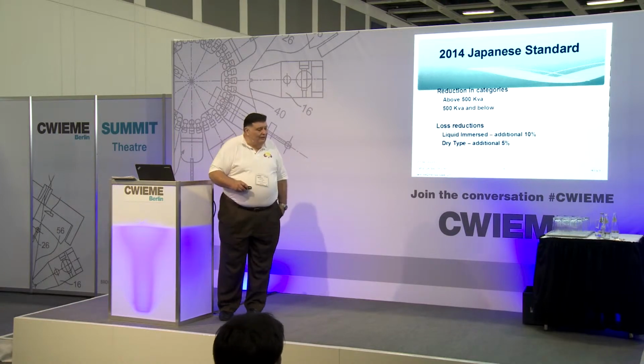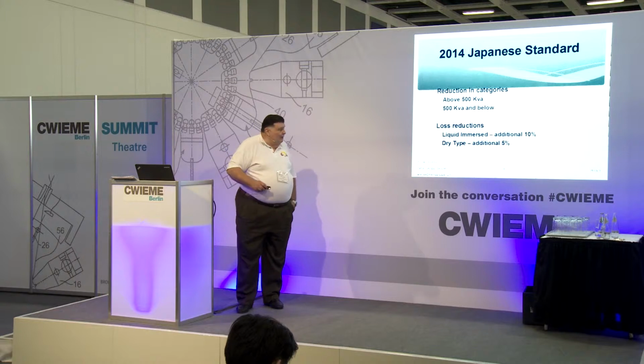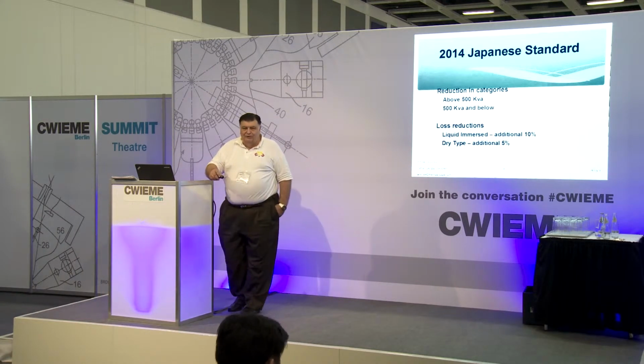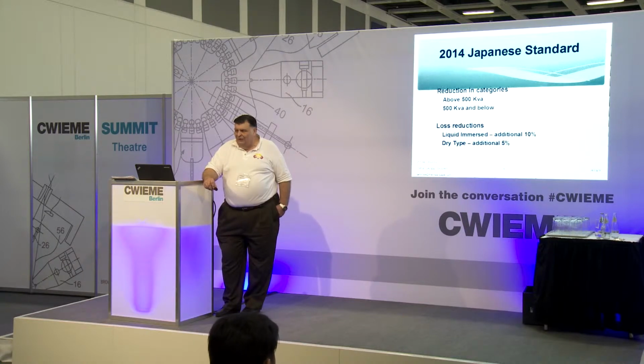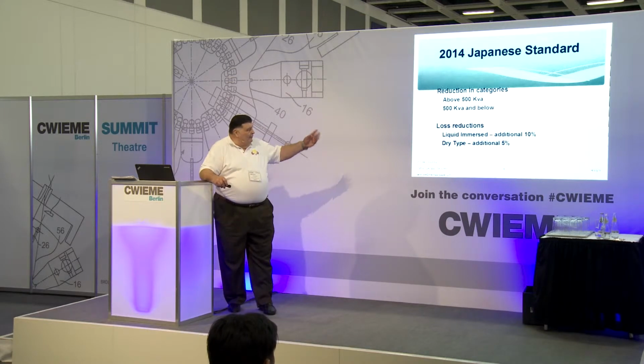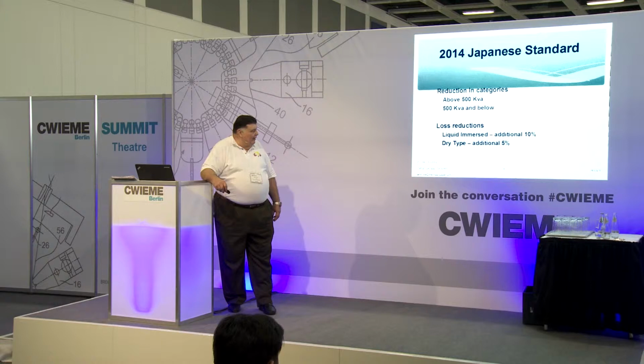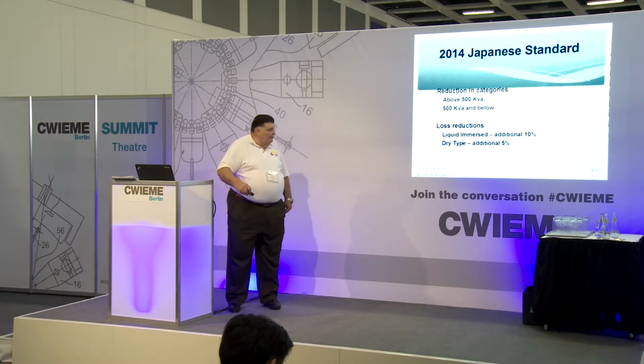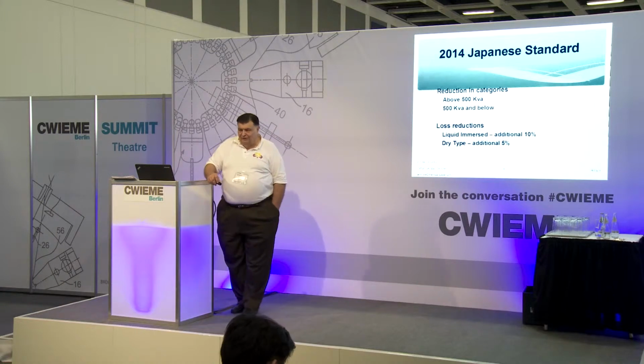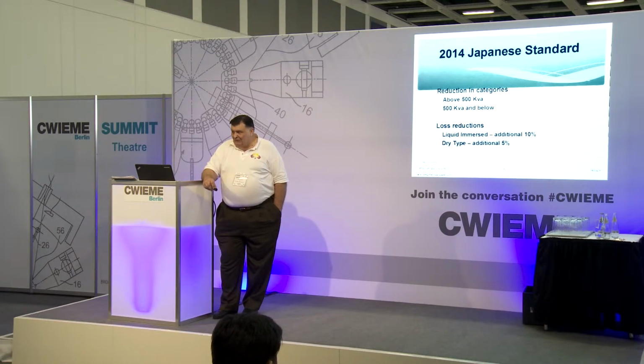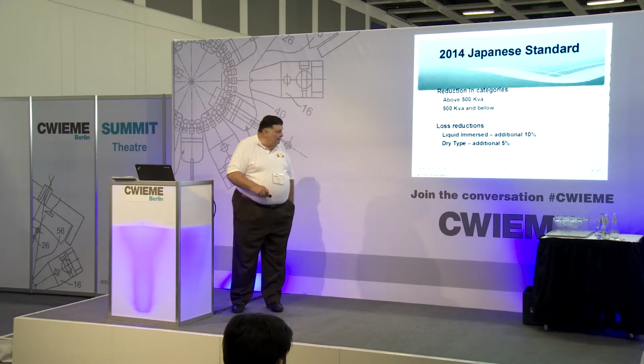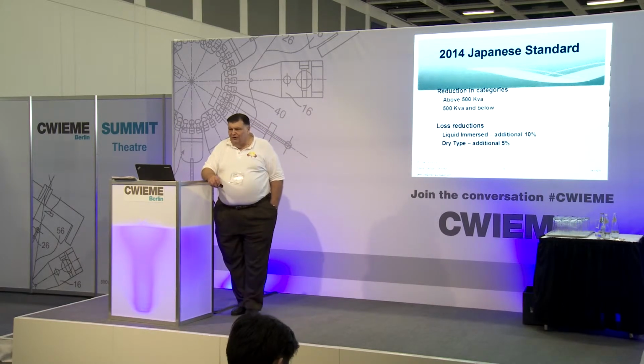The Japanese standard, the 2014 review: they're going to reduce the number of categories for transformers. They currently have about 7 categories, and they're going to reduce that to 2, 500 kVA and above and below 500 kVA. Loss reductions for liquid immersed transformers are about an additional 10%. And the baseline for that is more strict than the US standard now, so that's going to be a very significant reduction in losses for Japan. On their dry type, the loss reduction is about 5%.